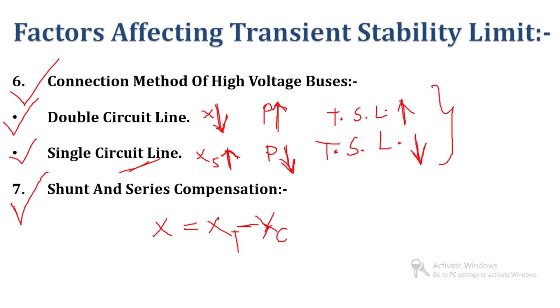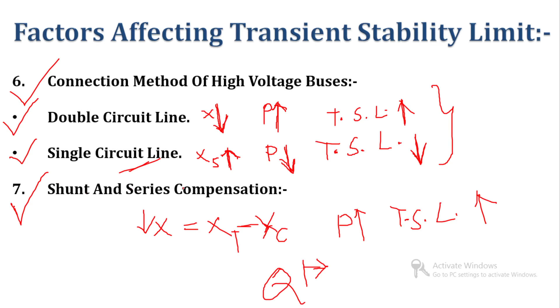And in the case of shunt compensation, it will provide reactive power to the line whenever there is a high loading situation. So in that way shunt compensation will reduce the reactive power loading on the generator. So in that sense it will improve the power transfer capability of the line and hence improve the transient stability limit. So that is the effect of shunt and series compensation on transient stability limit.